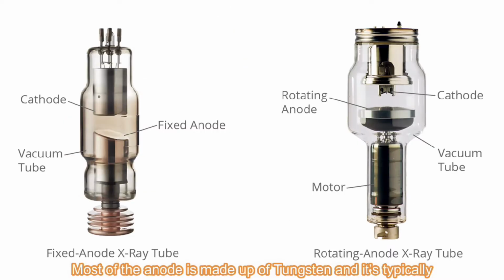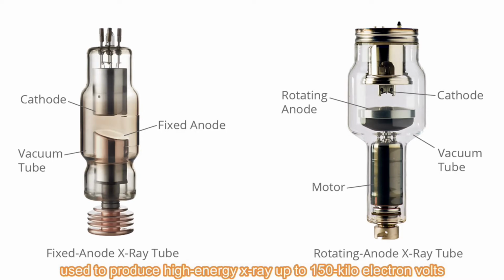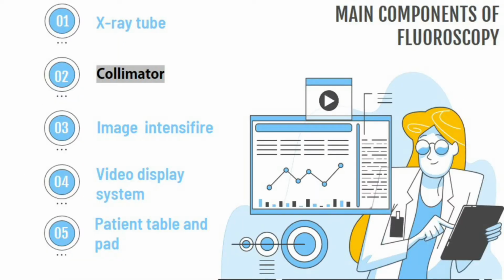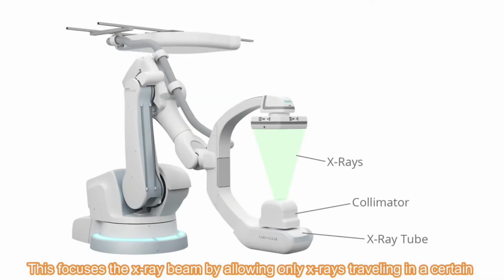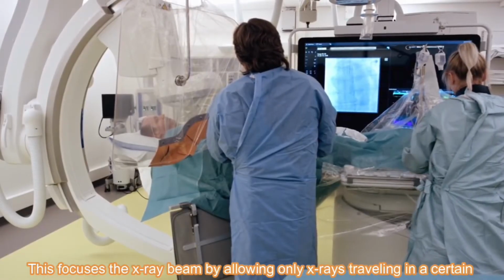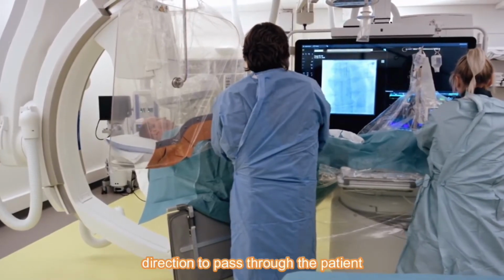Most of the anode is made up of tungsten and it's typically used to produce high-energy X-rays up to 150 kV. Collimator. This focuses the X-ray beam by allowing only X-rays traveling in a certain direction to pass through the patient. X-rays go through the patient and some of the radiation is absorbed.